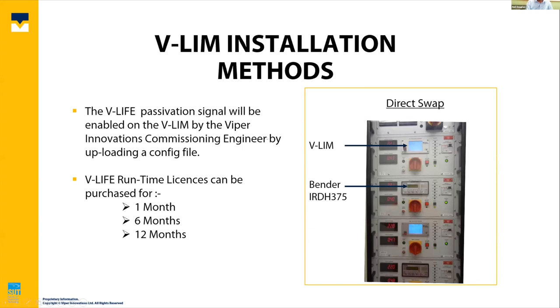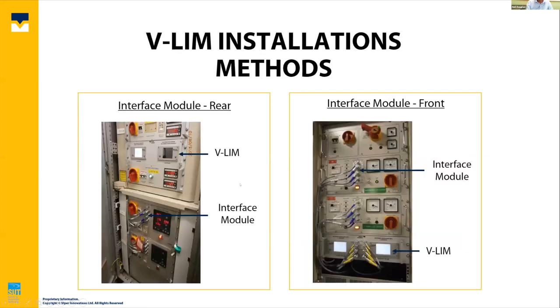I'll very quickly just go through some installation methods. Here's a rack where originally there were some Bender insulation resistance monitors. We had to take it out in order to get our V-LIM in. Once you've got your V-LIM in, you can apply V-life to that particular channel. And then here's some other installations. We've got a whole series of interface panels so that we can replace not just that particular style of insulation monitoring device, but a whole series through a range of interface modules. So it is a relatively quick process to take out what is already in the EPU, the electrical power unit, and replace it with our own.